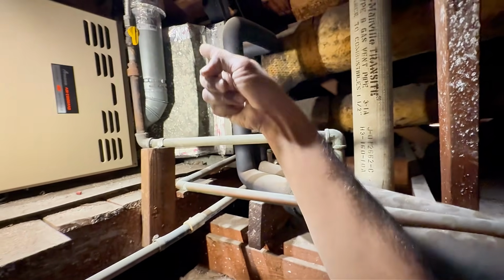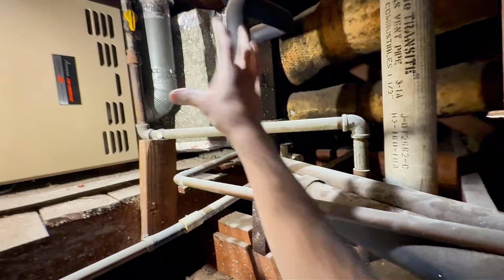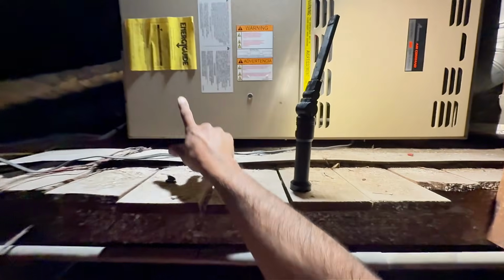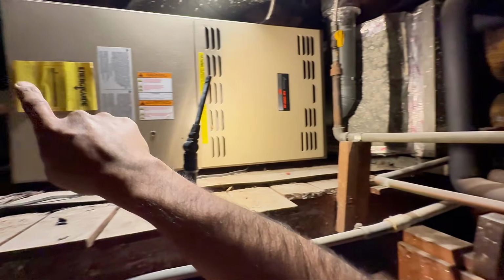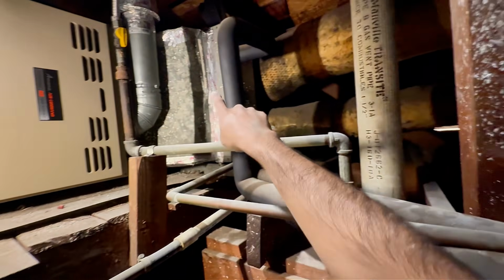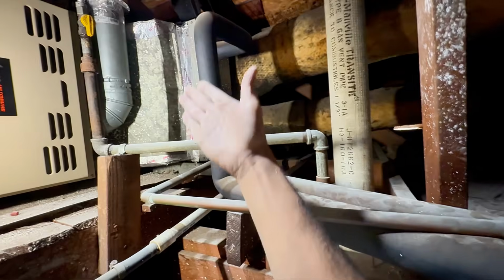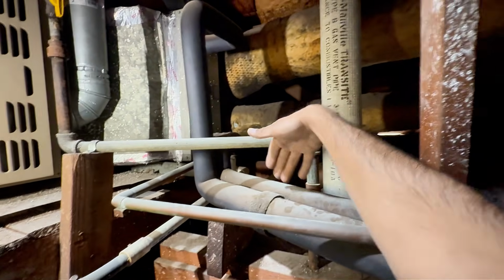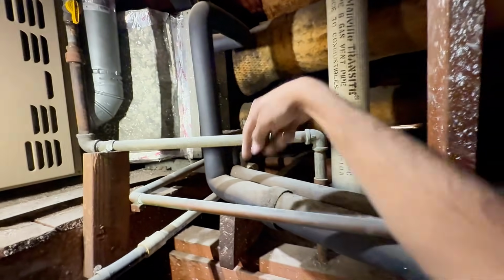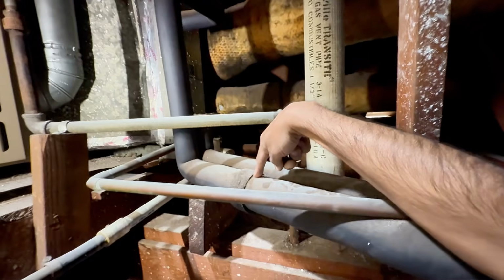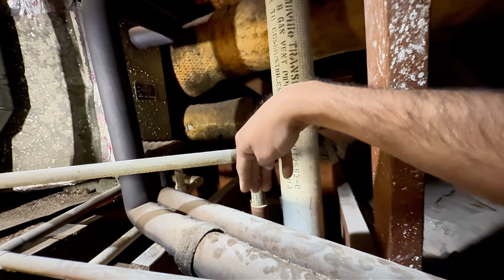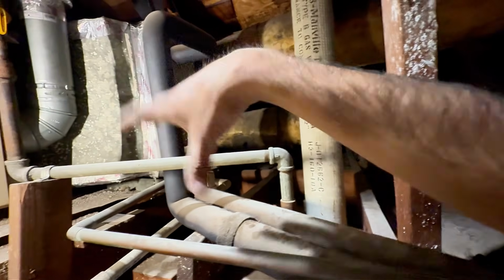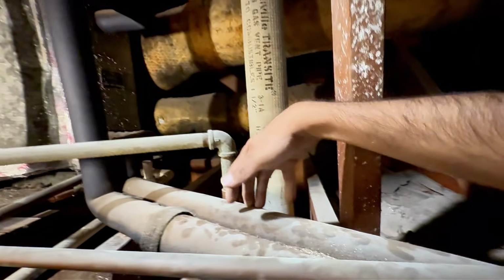Cold water, boom, and it fills that coil with cold water. So your return air on a hot day is warm, right? 80 degrees, boom, it comes out at 60 degrees because the water is cold. So the return pipe is going to be warmer. So let's say this is 35 or 40 degrees, and then this one, because it's collecting the heat from the warm air from the house, comes back as 55.